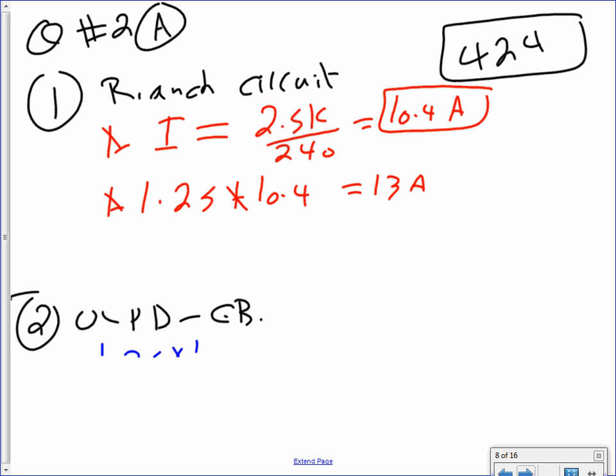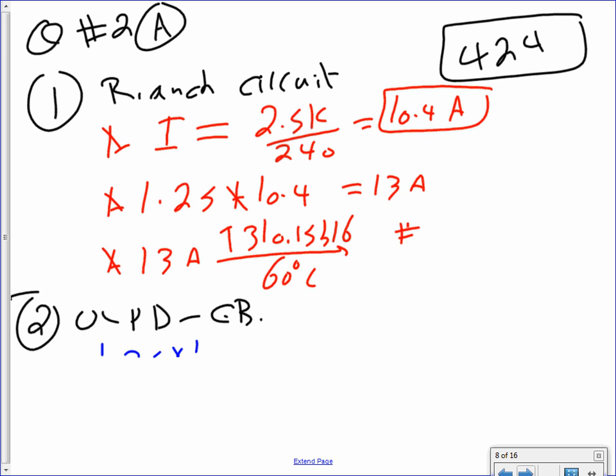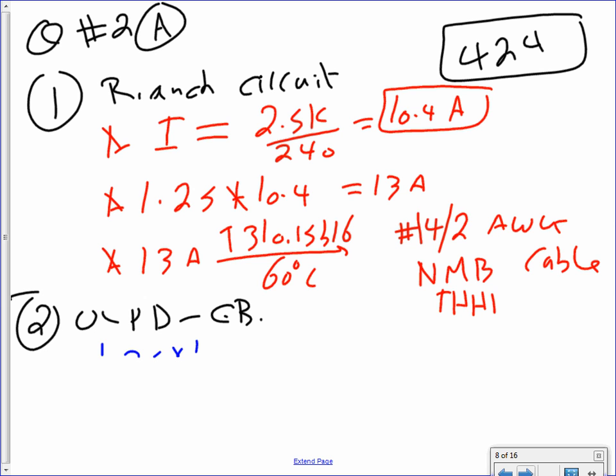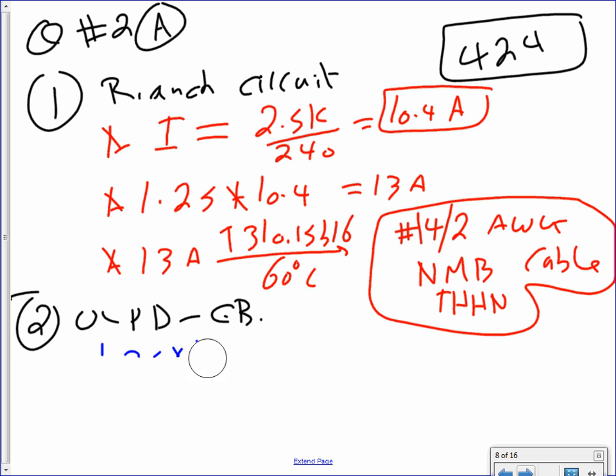13 amps, okay? Then you take your 13 amps and take this one to Table 310.15(B)(16) on the 60 degree column, and that will get you number 14 AWG NM-B cable with insulation THHN. The insulation in the cable is THHN. Done. So for this, that's all I need.